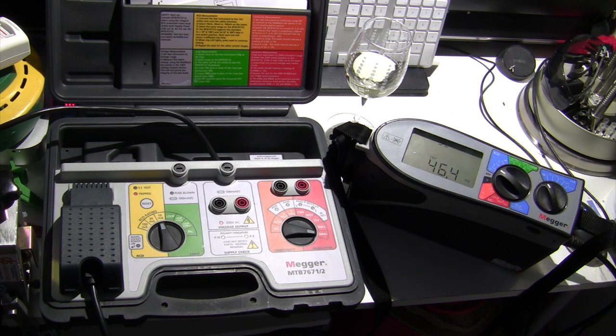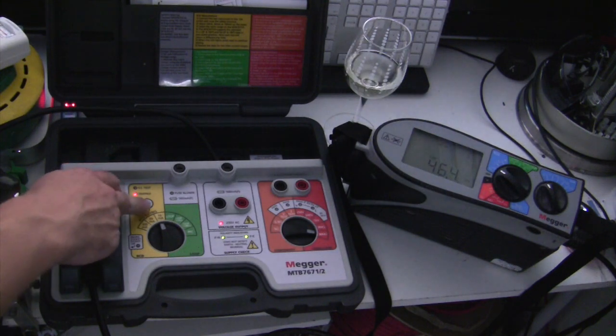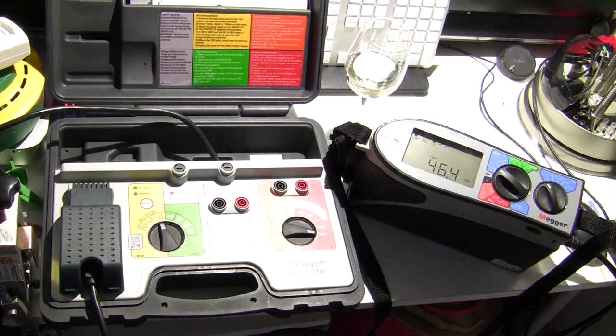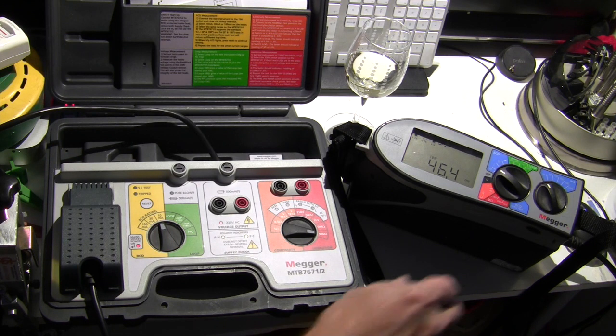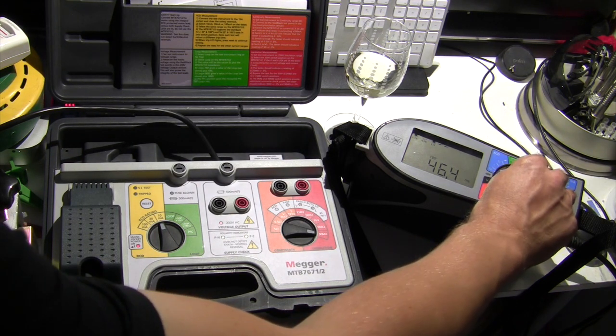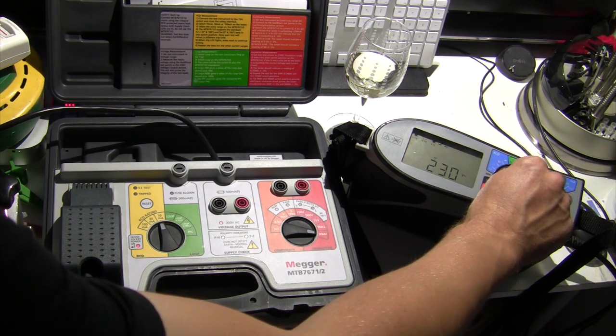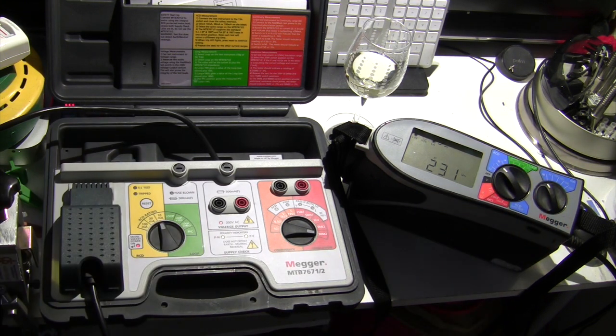And if I just turn off the light here, we can see again it's tripped, and I can reset it by pressing the reset button. Okay, now I'm going to switch to 5 times the rated current. So we're going to send 50 milliamps down the line now, and we should see a trip occur within 10 milliseconds on this particular test.